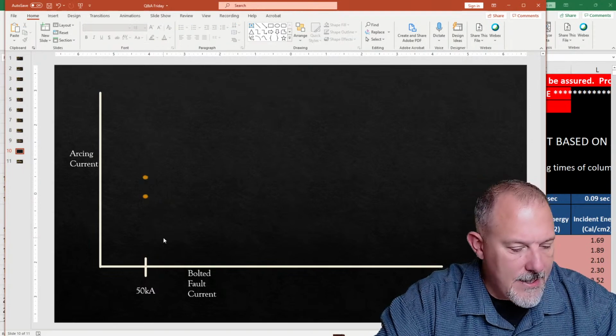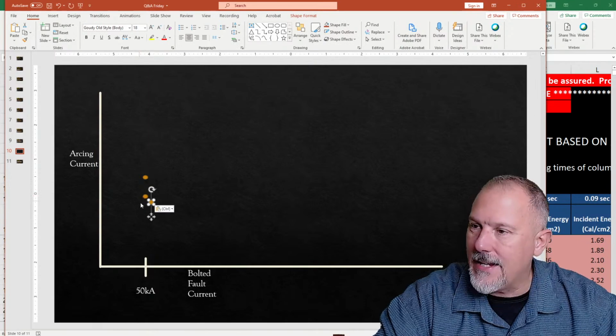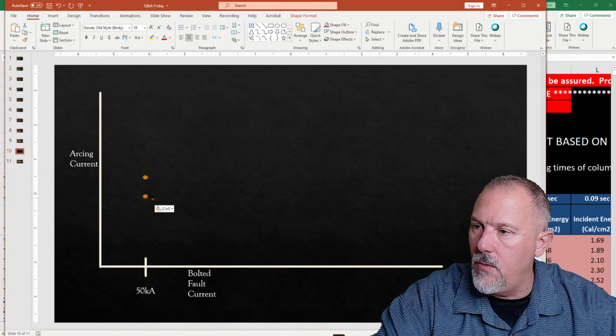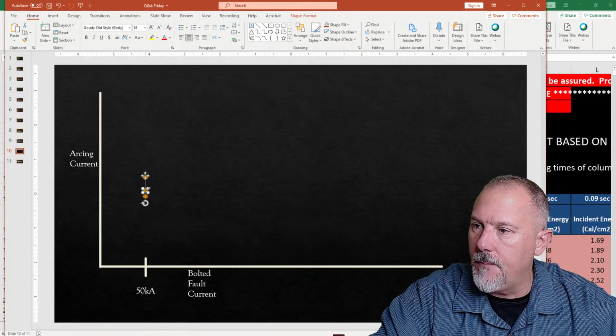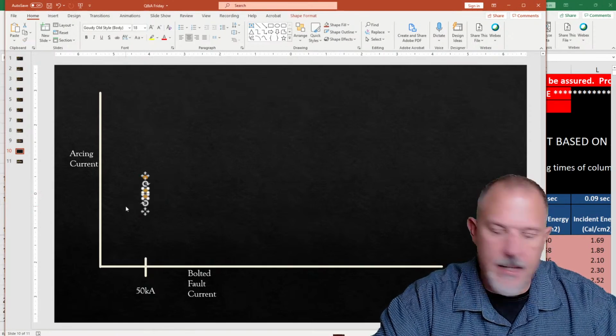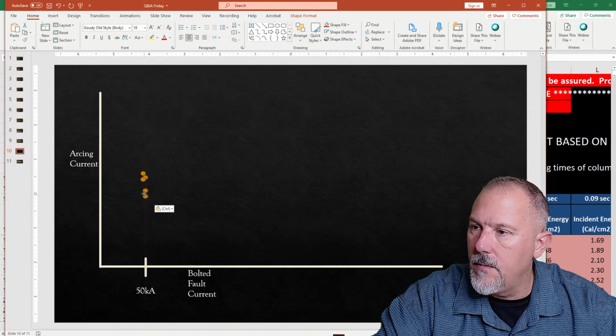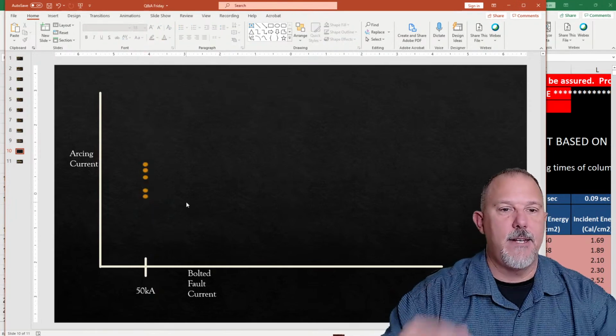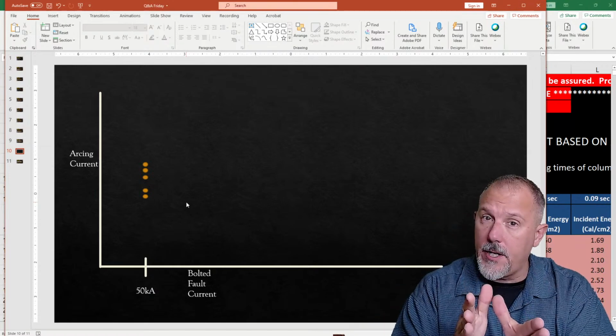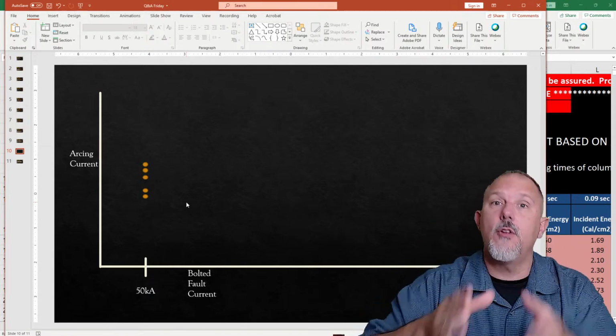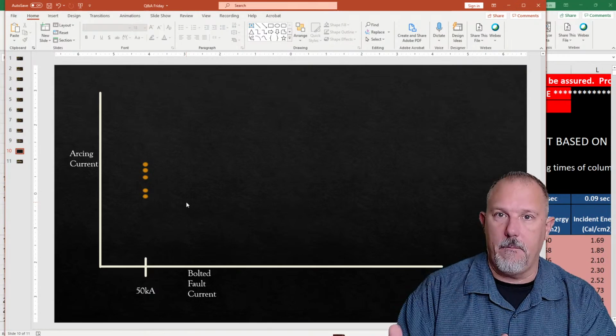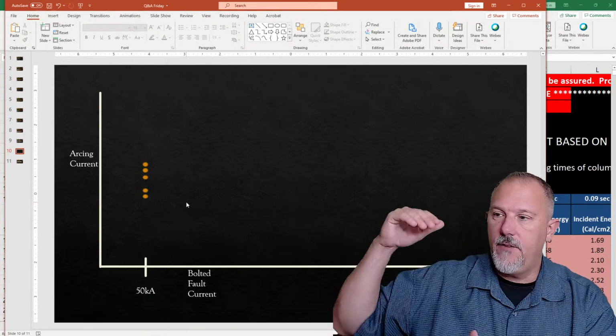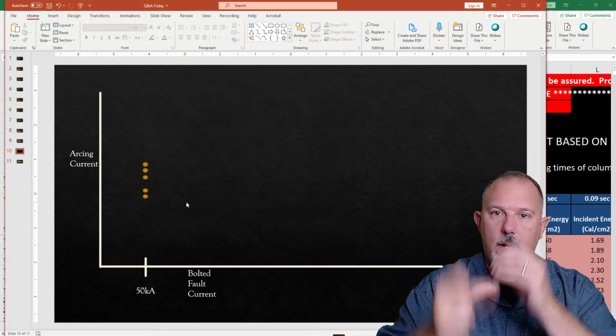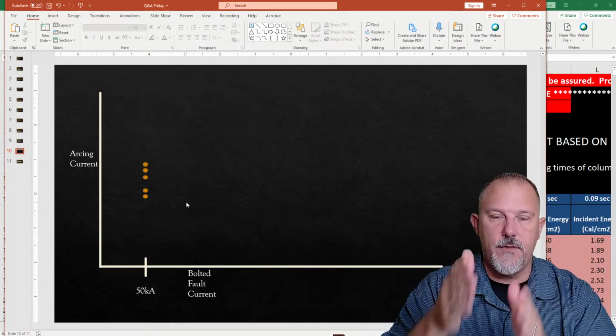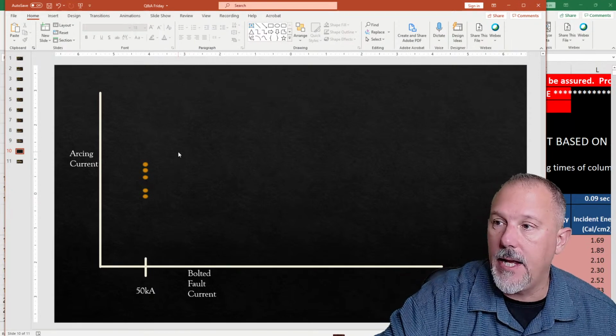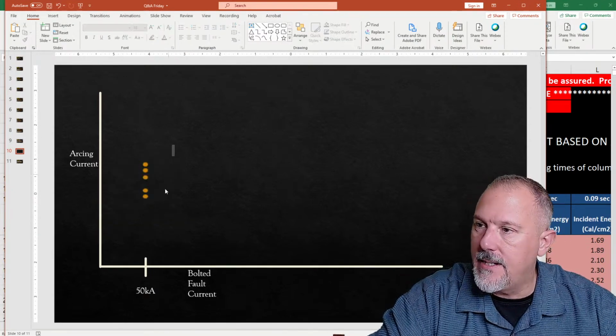And then what does he say? He says, set them up again, rack them again, and puts another one up. Whoa. He puts another one up there. And then maybe he does a few more, and that gives a range. So he gets different values, because what do we know about arcing? No two arcs are the same, they're like snowflakes. So for any given value of bolted fault current, he runs it over and over and over, and he gets various values of arcing current, and he plots those. So then he says, let's do it again.